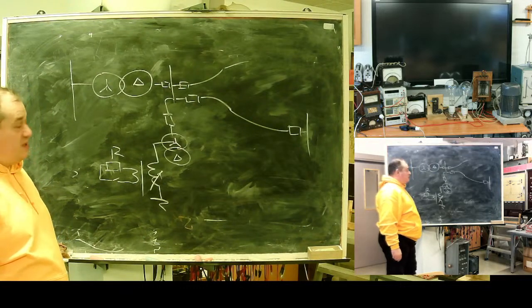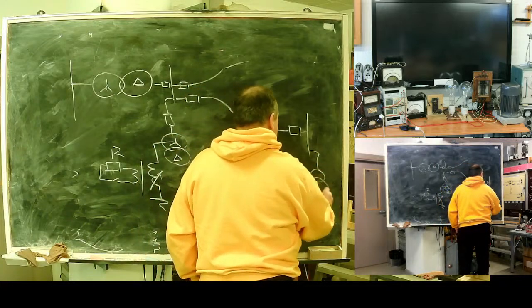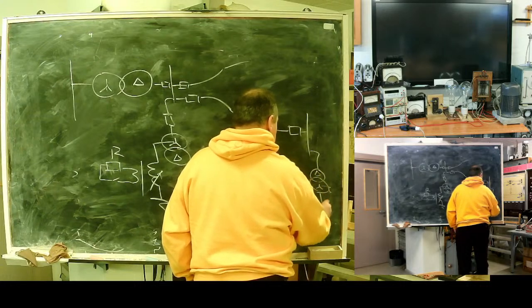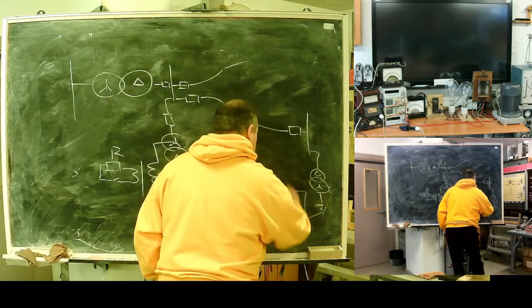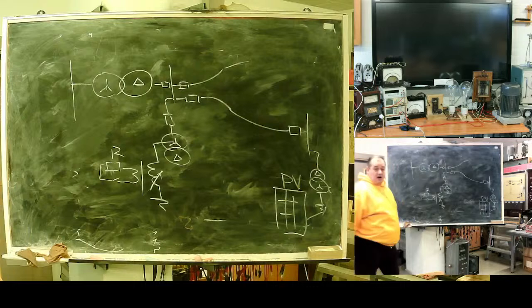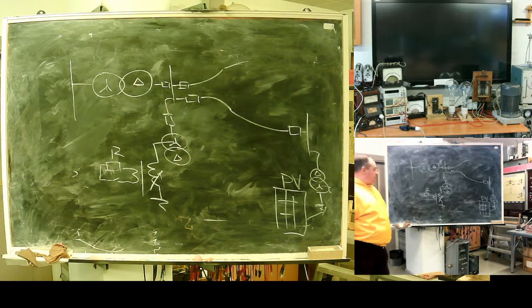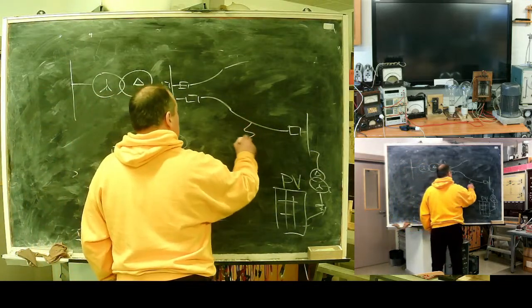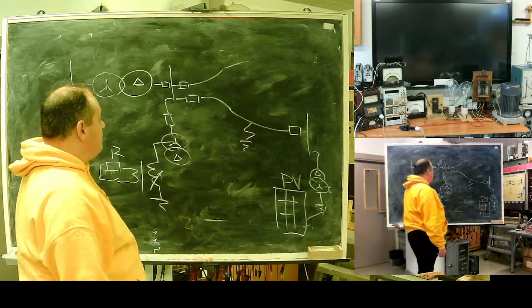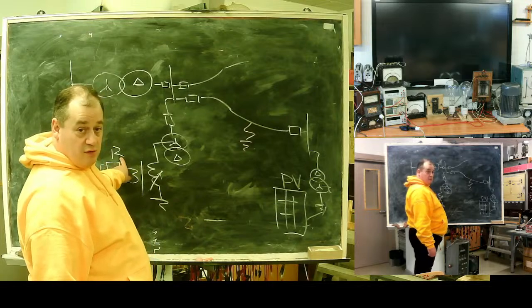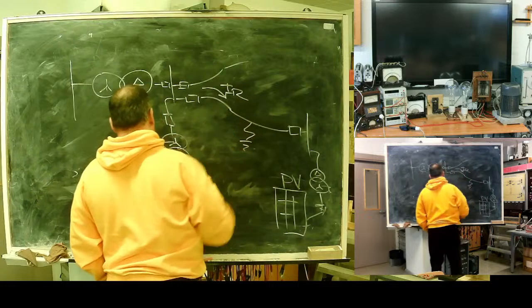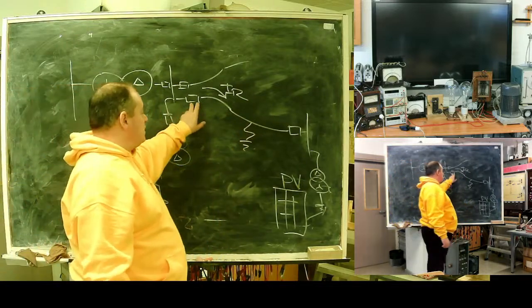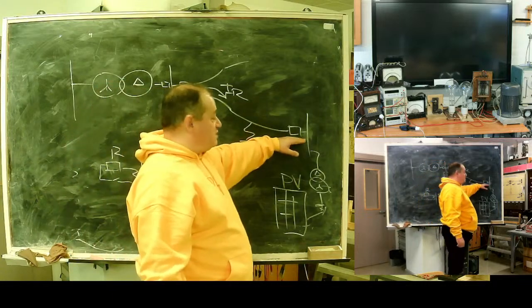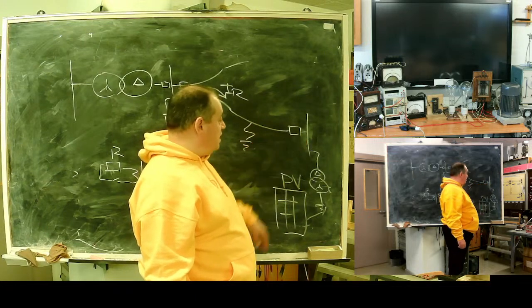nice network, low ohmic network, everything fine. Here you have a customer, our reality, who installed a photovoltaic system. Our nowadays reality, because it's profitable, we have a local subsidy. People do install photovoltaics on their roofs. Let's say we have an earth fault here. We will see nice earth fault current, mostly from this point, and good operating conditions for this protection. Really. And what about this one? Very weak current because of capacitance here.